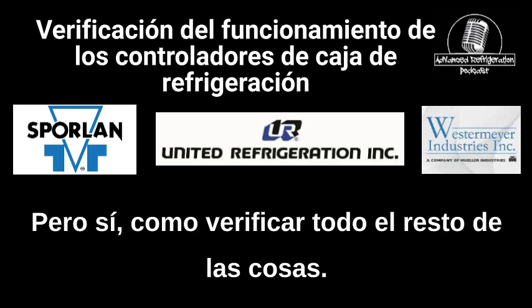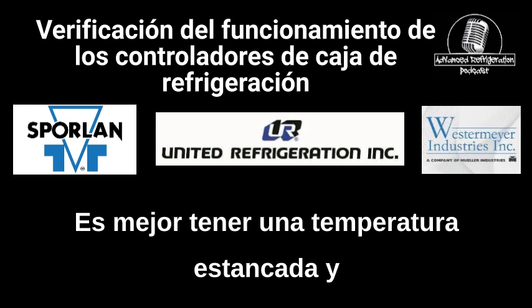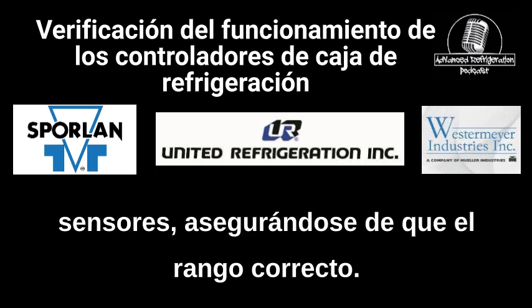But yeah, verifying all the rest of the stuff, it's better to have a stagnant temperature and/or pressure in order to verify this stuff. Make sure that you have the proper temperature sensors, making sure that they're the correct range.